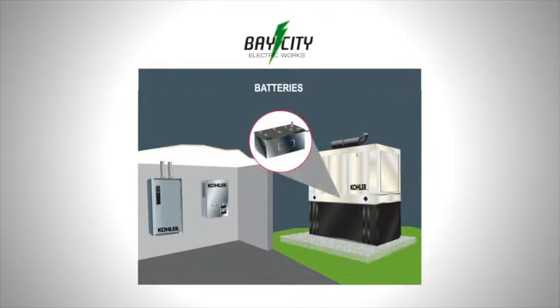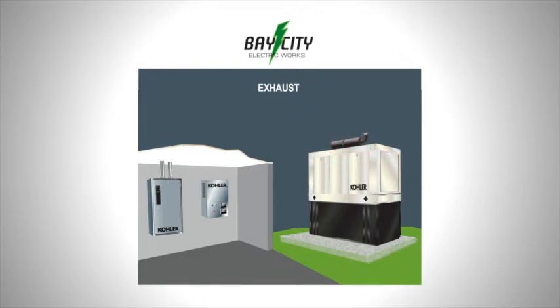Checking that the battery charger is operating as required — it is critical that the technician regularly checks battery condition. Checking the exhaust condition. Within the generator housing, the technician will check oil, air and fuel filters, all hoses, any belt tension, coolant levels, and check for any fuel leaks.